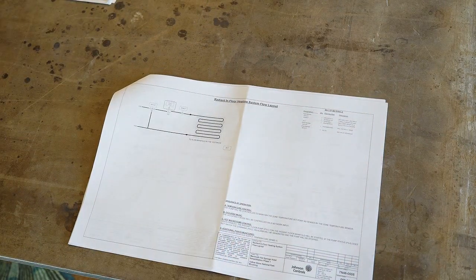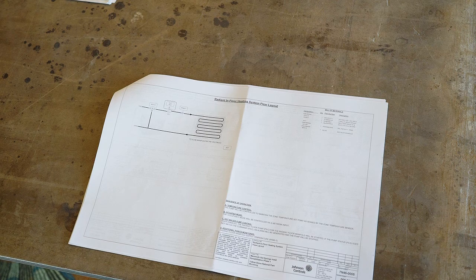In the vestibule coming in from outside on the front end of the building, there's some radiant in-floor heat. So basically we have a three-way valve to let hot water into that slab, and there's a pump that pumps the water through the slab, and we have a temperature sensor on the supply. So we'll modulate to maintain a temperature based on that hot water supply temperature sensor, and we'll modulate the three-way valve. Okay, so as the temperature gets off set point and it calls for heat out there, we'll turn on the pump, we'll open up the three-way valve and inject hot water out into the system to heat it up. Those are located, again, down in that crawl space area, so I'll show you where those are located.